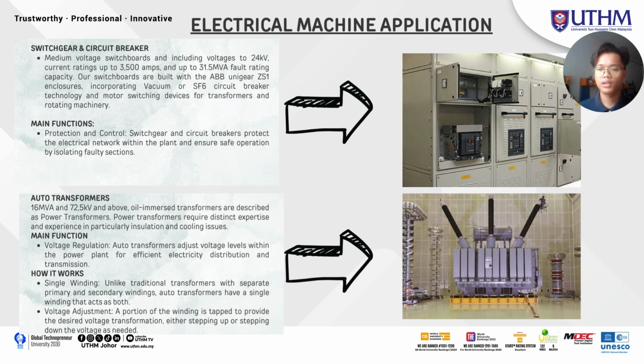And last is the auto transformers, 16 MVA and 72.5 kilovolt and above. Oil immersed transformers are described as power transformers. Power transformers require distinct expertise and experience, particularly in insulation and cooling issues. For the main function, voltage regulation, auto transformers adjust voltage levels within the power plant for efficient electricity distribution and transmission. And how does it work?